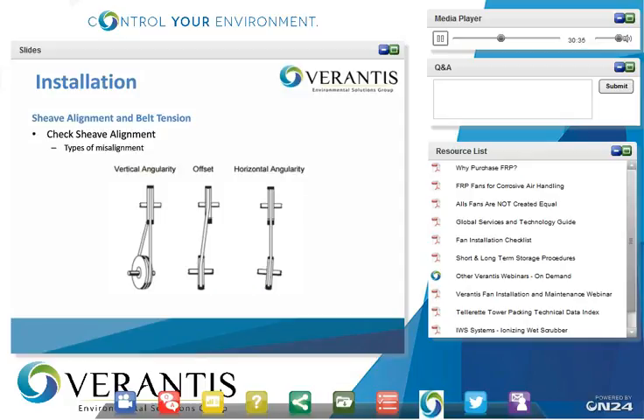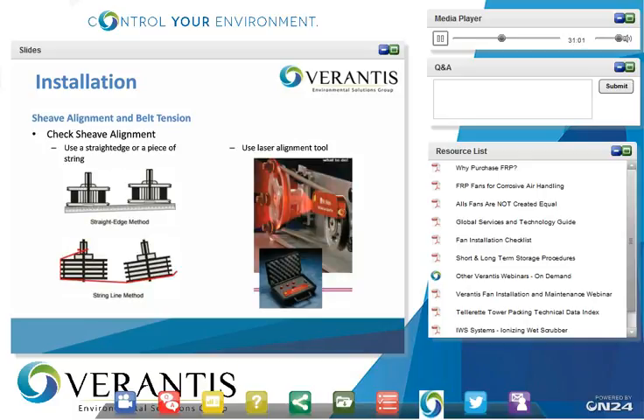Installation, sheave alignment, and belt tension. You need to always recheck your sheave alignment when the fans arrive on site. Your vertical angularity, the offset, and horizontal angularity are just some of the misalignments. On sheave alignment, you can use a straight edge or a piece of string to check the alignment of the sheaves, or you can use a laser alignment tool, which works very, very well.